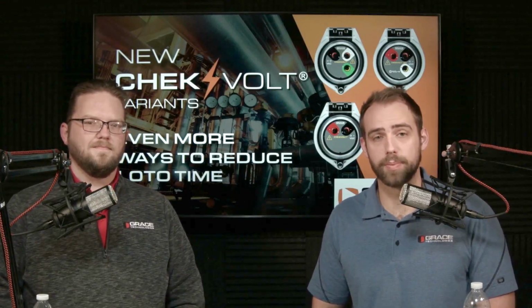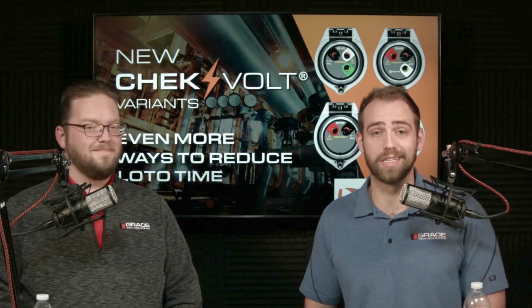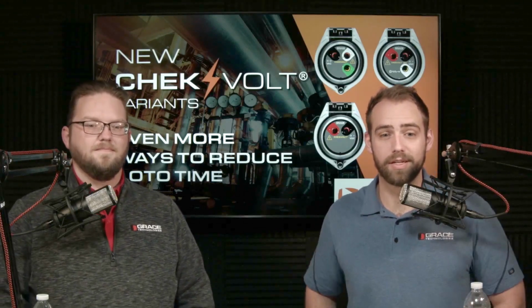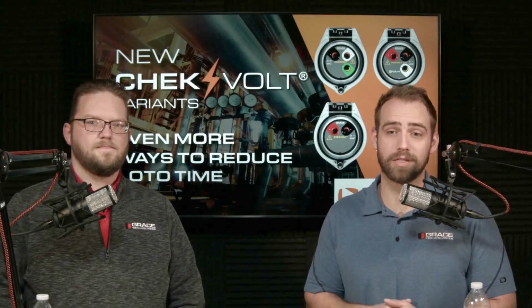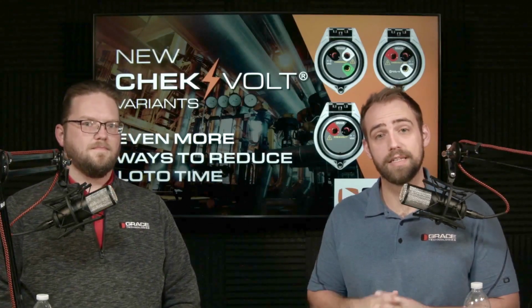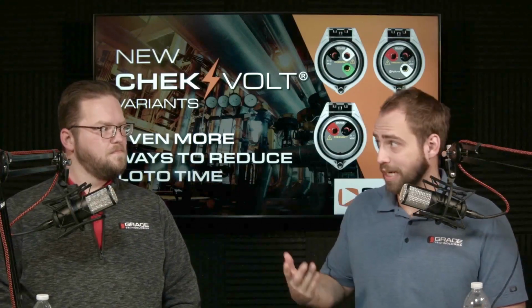Typically when end users implement the Chek-Volt, the feedback we hear is people are receiving a return on investment in just 2 or 3 lockout tagouts. That's mainly because, since you can test for absence of voltage with the panel door closed, safety allows you to confirm absence of voltage at the point of work without suiting up in arc flash PPE gear, which saves quite a bit of time. A lot of that return on investment comes from that time savings.